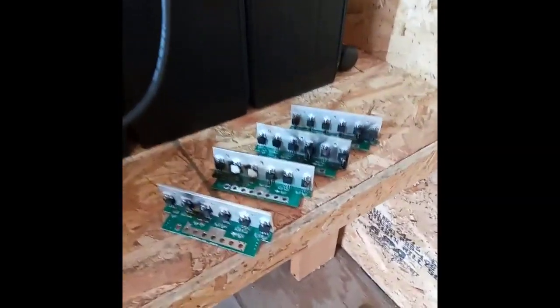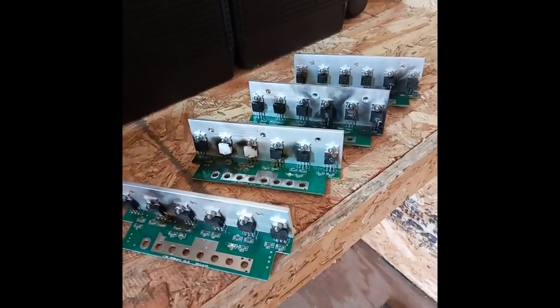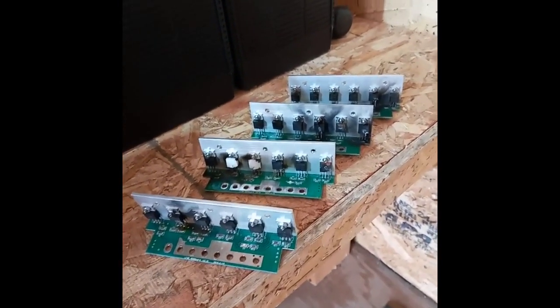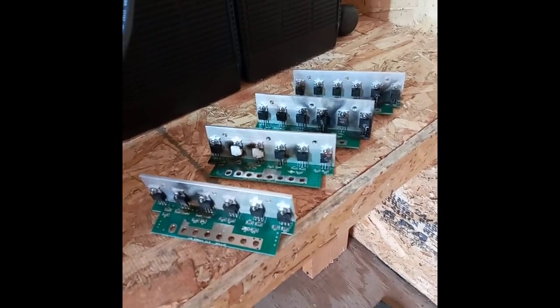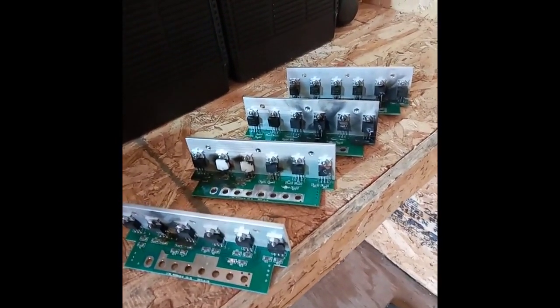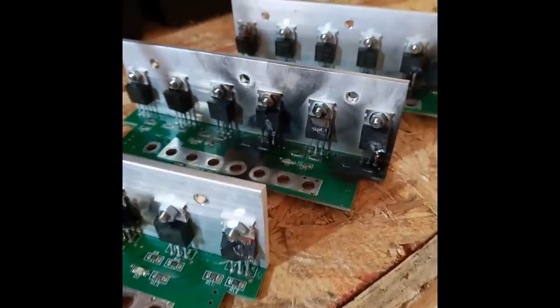Once the parts finally arrived, I changed over the board and all four MOSFET boards — there are four MOSFET boards in total. This is what they look like. I had one bad board and three used boards, and received four new ones. As you can see, the boards have charred damage on them — these things were just absolutely destroyed.